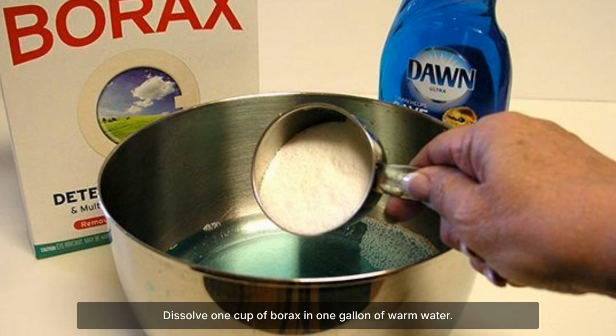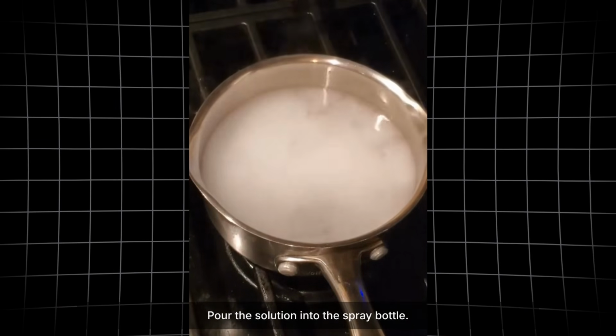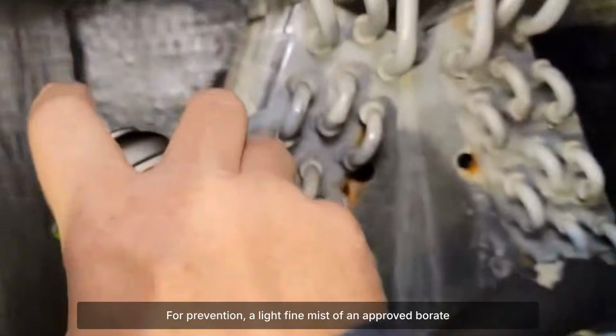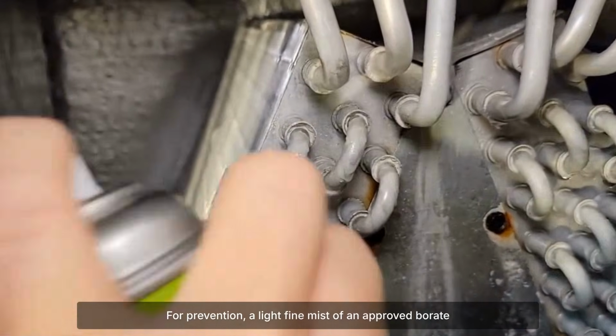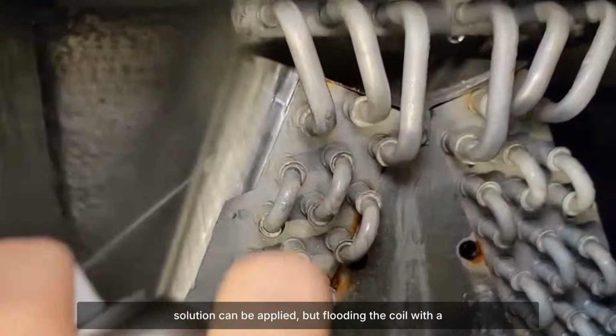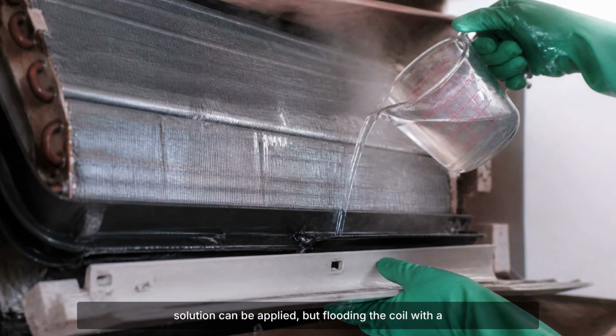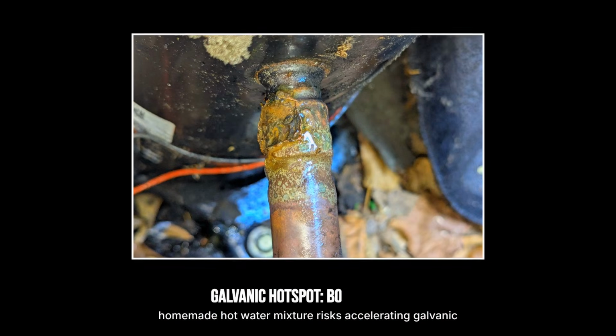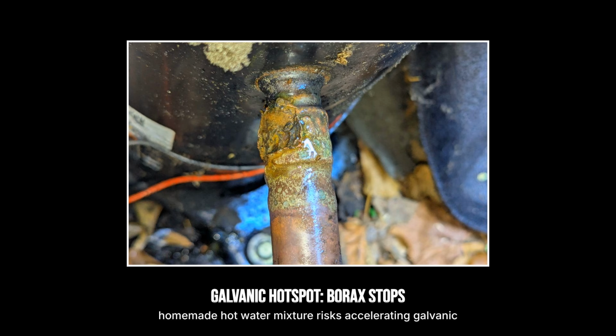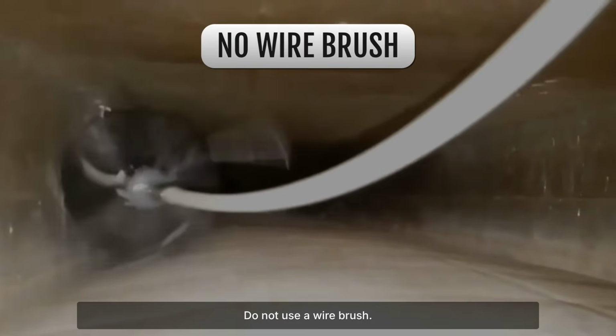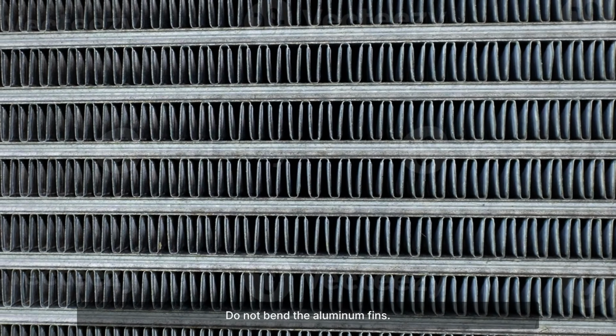Dissolve 1 cup of borax in 1 gallon of warm water. Stir until fully dissolved. Pour the solution into the spray bottle. If your coil is accessible and dirty, it must be cleaned first. For prevention, a light fine mist of an approved borate solution can be applied, but flooding the coil with a homemade hot water mixture risks accelerating galvanic corrosion on the copper aluminum joints. Do not use a wire brush. Do not bend the aluminum fins.